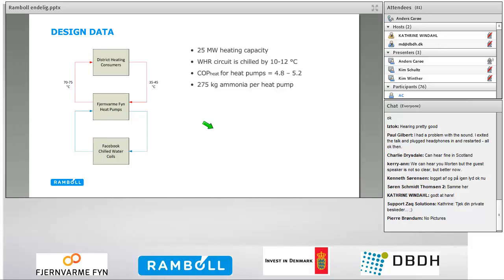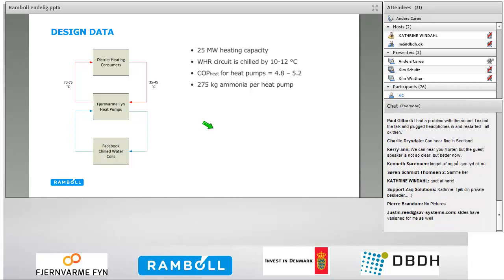The design COP for the heat pumps is around 4.8 if the supply temperature is 75 degrees Celsius and around 5.2 if the supply temperature is 70 degrees Celsius. This means that for every unit of electricity that the heat pumps consume, they will produce around 5 units of heat. And the COP for this particular plant is around 30 to 40% higher than what could be expected from a similar air source heat pump. Each of the 9 heat pump units have their own separate ammonia circuit, and the ammonia charge per heat pump is around 275 kilograms. This is less than 100 kilograms per megawatt of heating capacity, and this relatively low ammonia charge is an important safety feature of the plant.